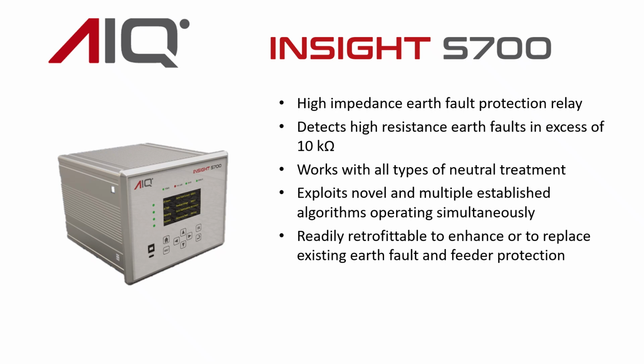It detects high resistance earth faults in excess of 10 kiloohms, works with all types of neutral treatment, and exploits novel and multiple established algorithms operating simultaneously, and is readily retrofittable to enhance or to replace existing earth fault and feeder protection.